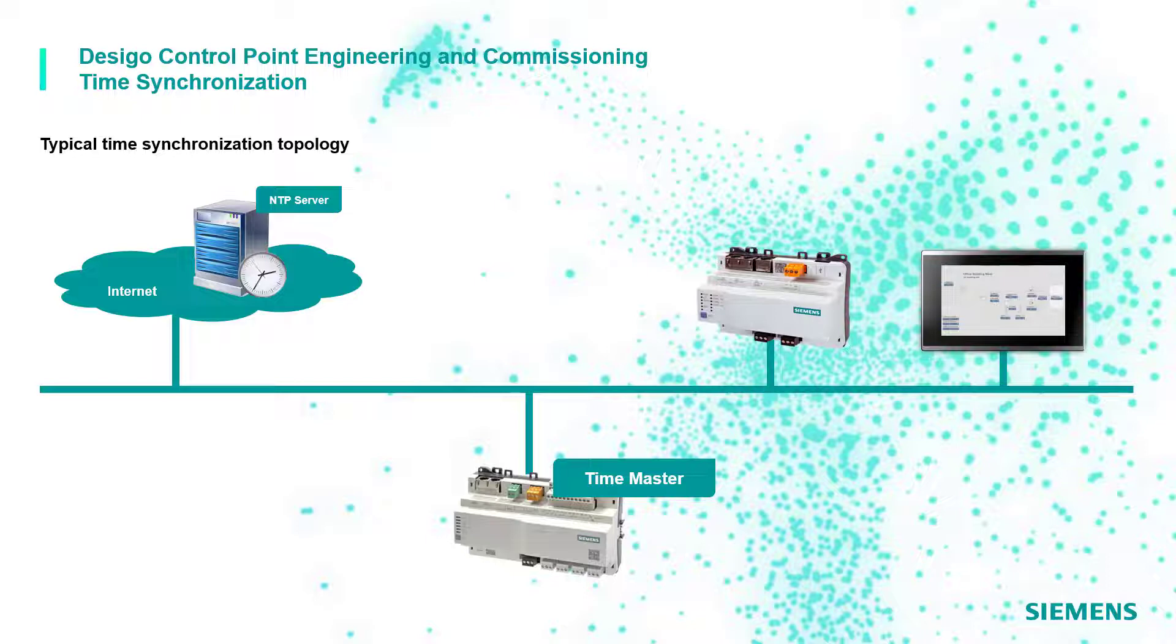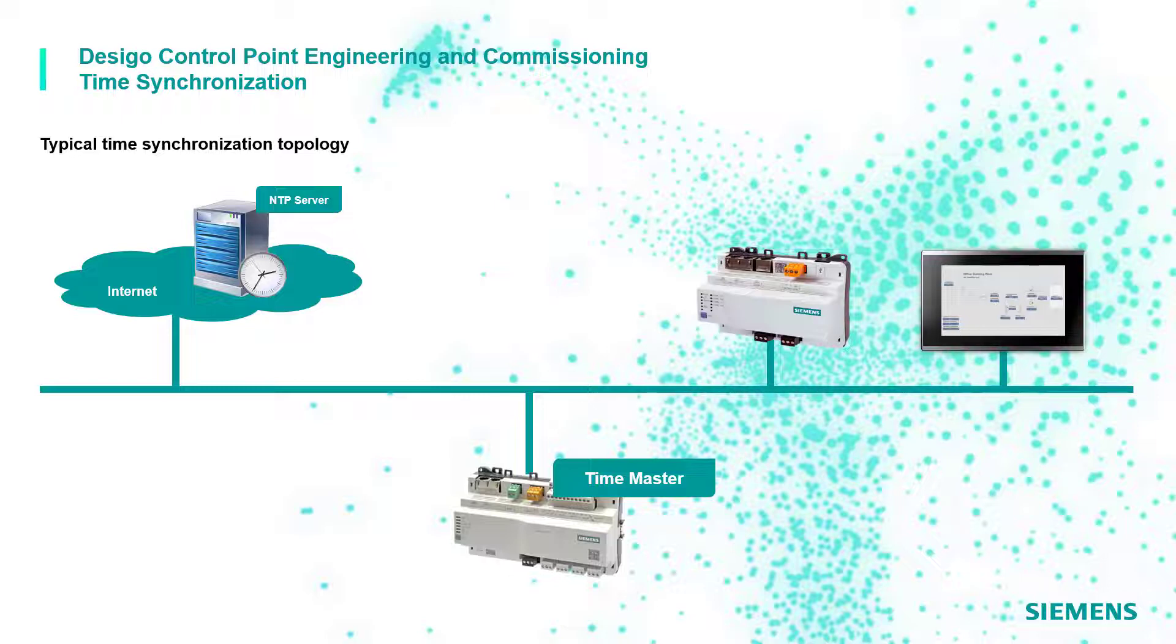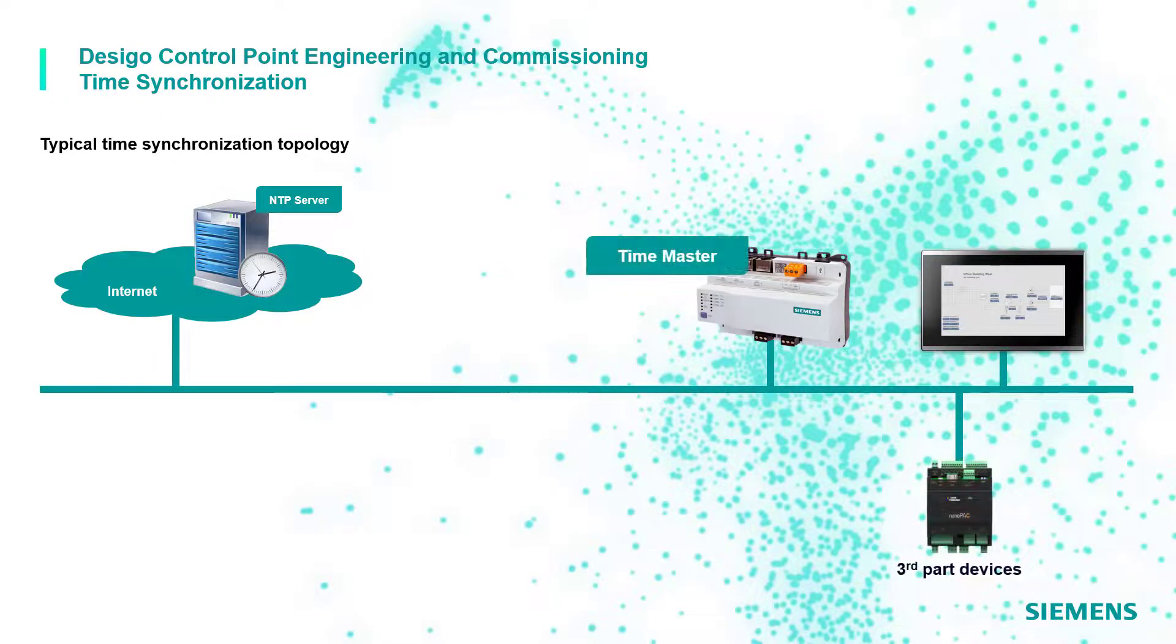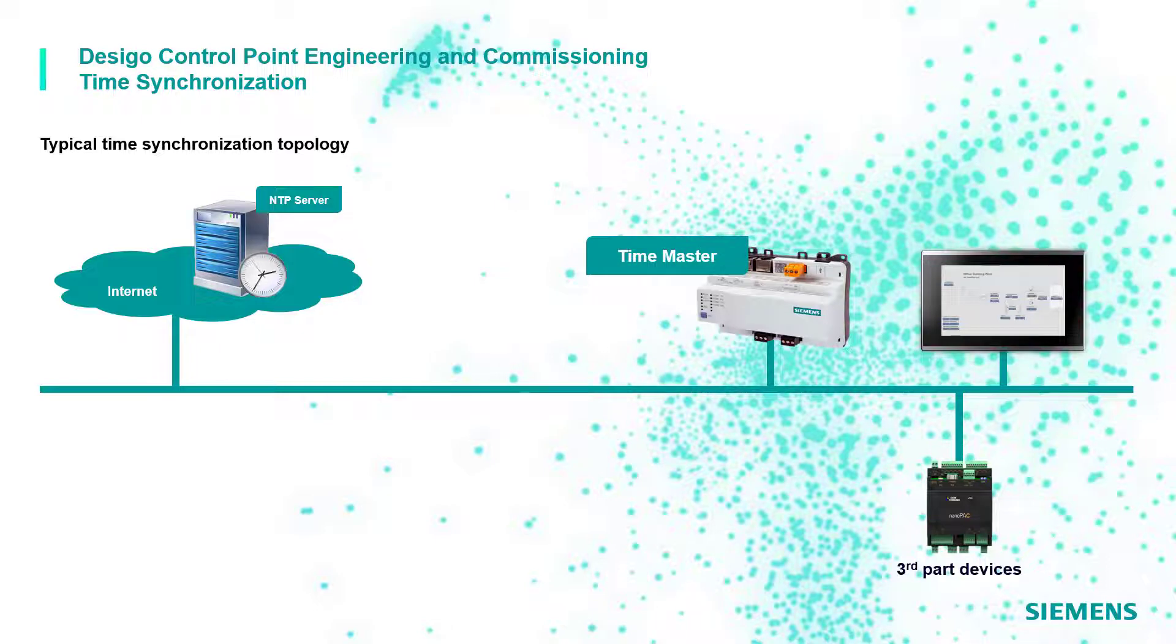Desigo control point devices offer now the possibility to cover this function as well, so it is now possible to set a PXG3 web server or even the PXM touch panels as Time Master. But we recommend to do that only if no automation stations are available.